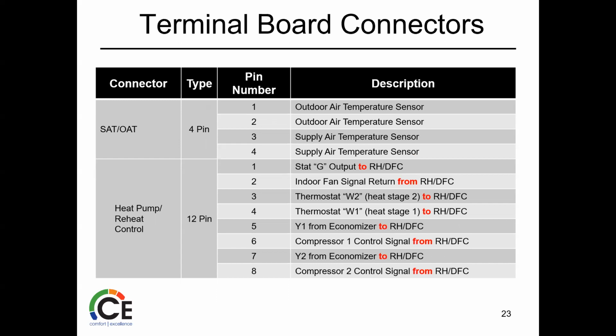That's just where your sensors tie in. Heat pump or reheat control, again, that's the output here. Indoor fan signal, there's a return. So in most of these, there's always a supply and return. Again, Y1 from economizer, compressor 1 signal. So everything is back and forth. So when you're talking troubleshooting, and we're going to talk a lot about the path of these signals to try and help guys diagnose these things while you're on the roof.